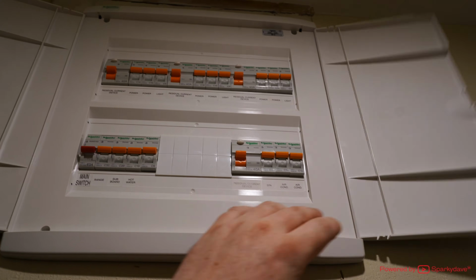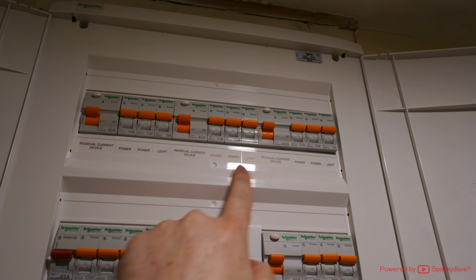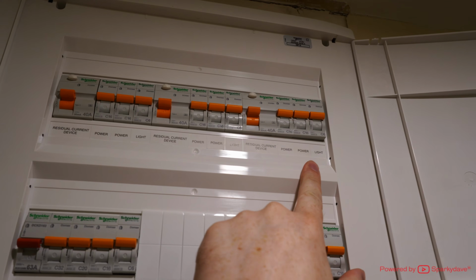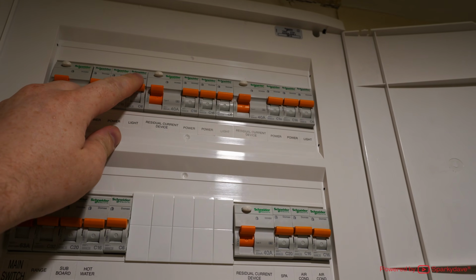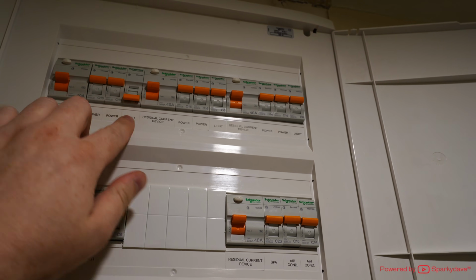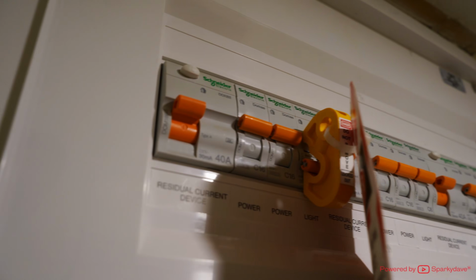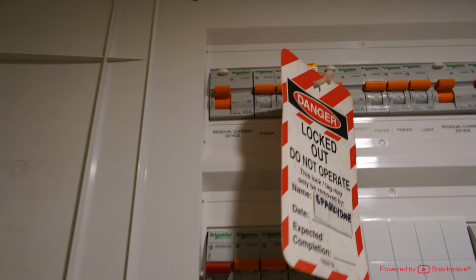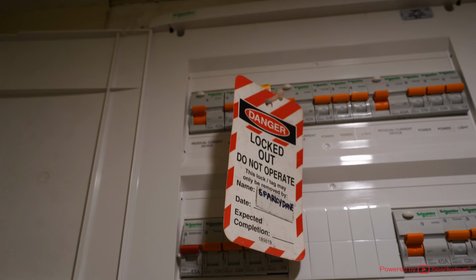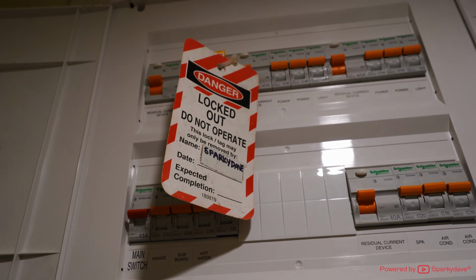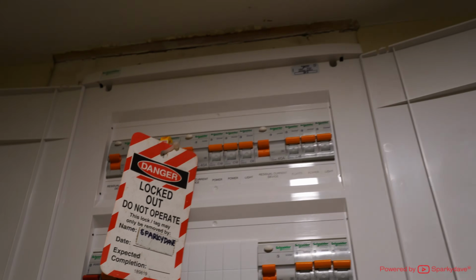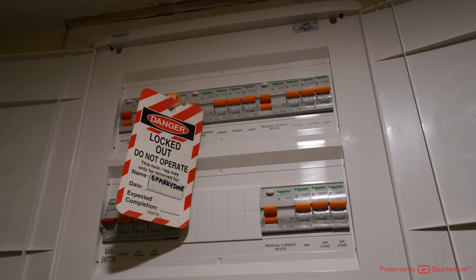Locate the appropriate switchboard and flick the circuit breakers labelled lighting off until the wall light ceases to operate. Check the wall light each time a different circuit breaker has been switched. Once the correct circuit breaker has been identified, it must be locked out and tagged to prevent any other person from accidentally re-livening the circuit while electrical work is taking place.